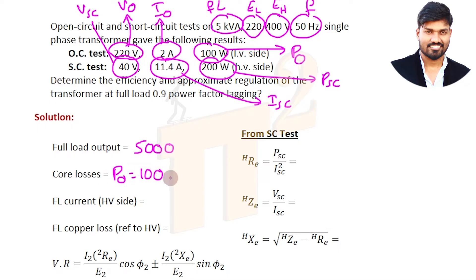Full load current on HV side: total power is 5000 and HV side is 400 volts, so 5000 by 400 equals 12.5 ampere. This is the HV side full load current. Here it is only drawing 11.4 ampere, so P_SC is not full load copper losses because current is not full load current.